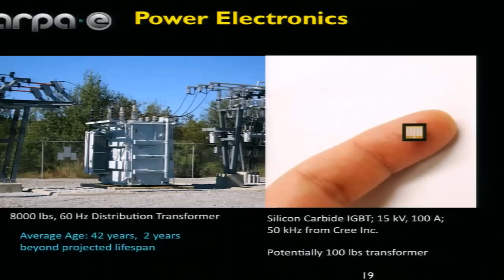They're now trying to modulate this at 50 kilohertz instead of 50 hertz, because doing so shrinks the inductor and transformer size dramatically—instead of 8,000 pounds, it could be about 100 pounds, small enough to fit in a suitcase. We believe this, whether silicon carbide or gallium nitride based, is the future of power electronics for DC-DC and DC-AC conversion. It could be the key to reducing terminal costs for high-voltage DC transmission, making it more cost-effective than AC transmission—Edison winning out over Tesla, in a sense.